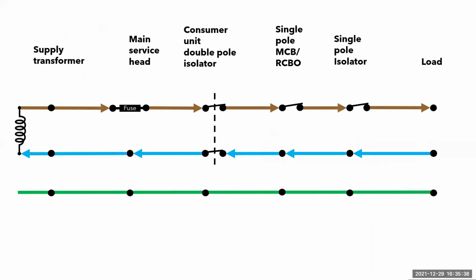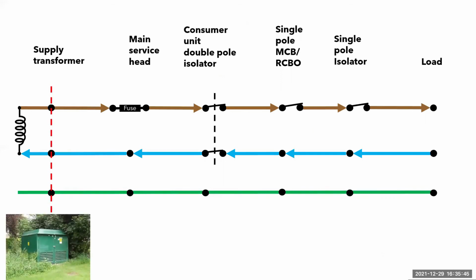Here, I have drawn up a very basic flow diagram showing the supply coming in from a local transformer, the type that you would find out in the street, perhaps in an enclosure like this one or behind a fence with warning signs posted around the perimeter. Next, we have the service head, which houses the main fuse and is usually controlled by the local distribution network operator or DNO. These are usually sealed with a metal crimped tie to avoid tampering.